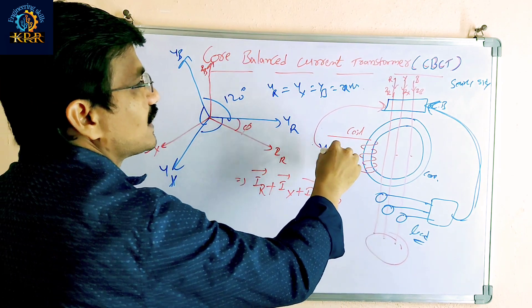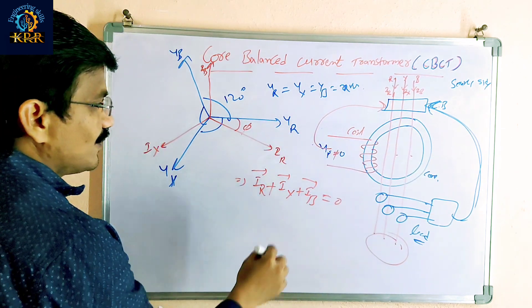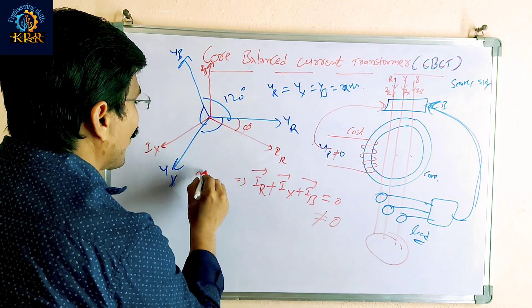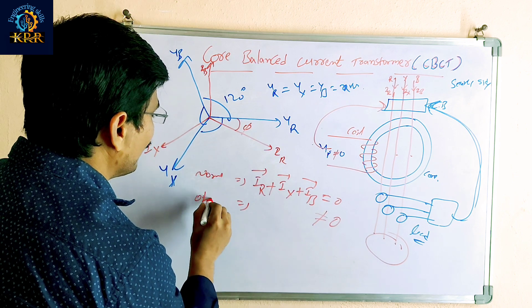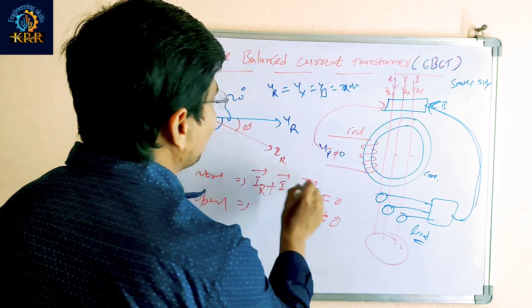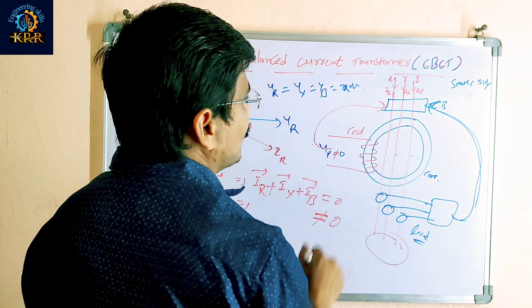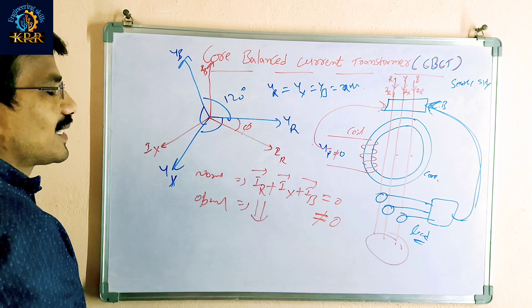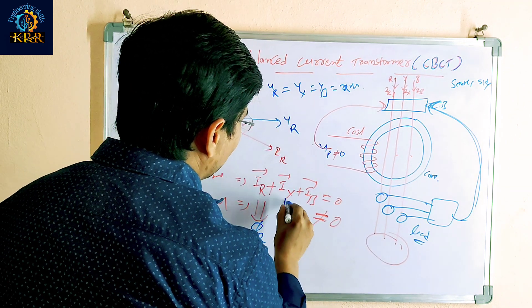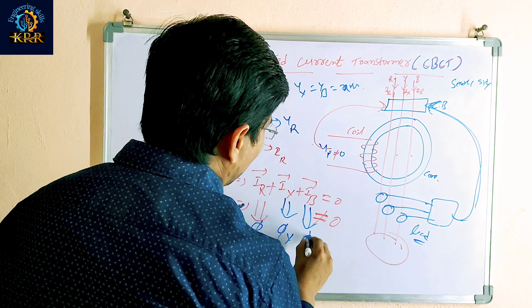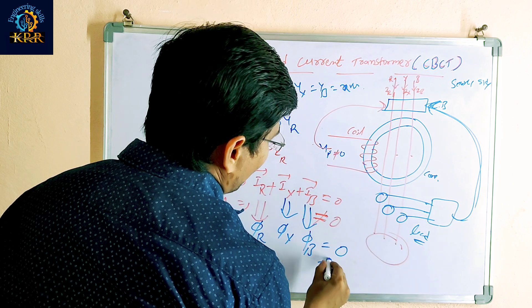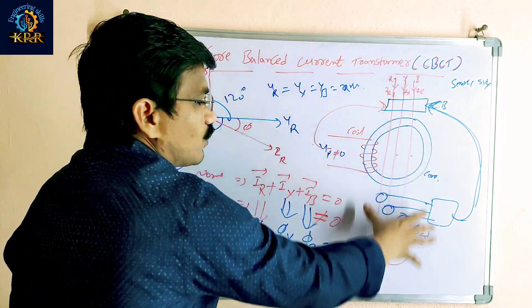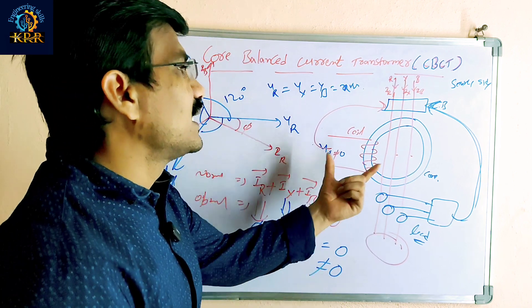In normal operation, the vector sum of all currents is zero, so there is no voltage across the coil and no command is given to the circuit breaker — no tripping. Each phase IR, IY, IB generates a corresponding flux: R-flux, Y-flux, B-flux. The resultant flux is also zero in normal operation, meaning no voltage is generated across the coil and the circuit breaker receives no command.